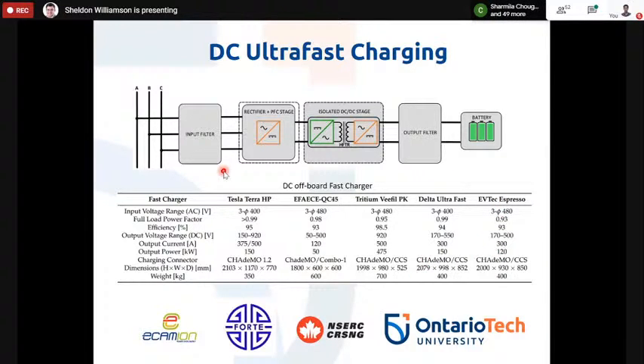In a fast charger, you tap into a distribution line, so you're already working with high voltage at AC distribution level, in kilovolts. You have the input filter, rectifier and PFC stage, then the isolated DC-DC stage, and finally the output filter and charging of the battery. Inside the isolated DC-DC stage, you have the high frequency transformer, a DC to AC inverter, and an AC to DC rectifier on the secondary side, like a typical power supply.